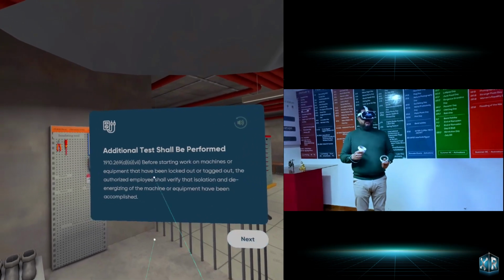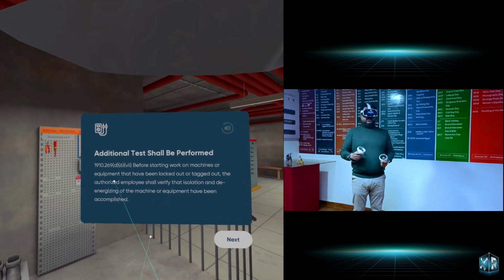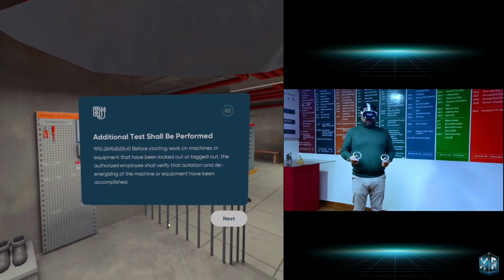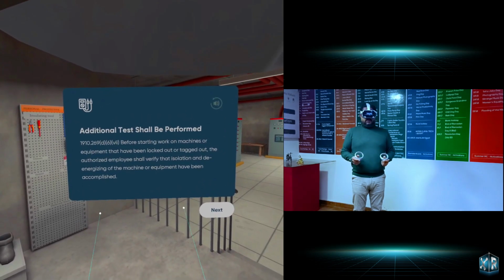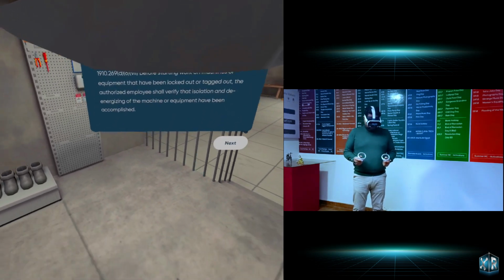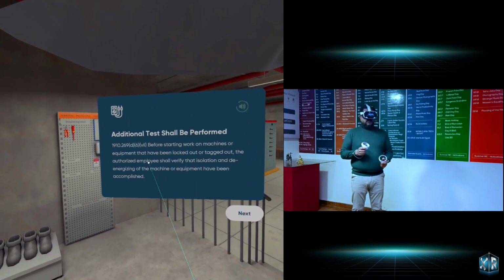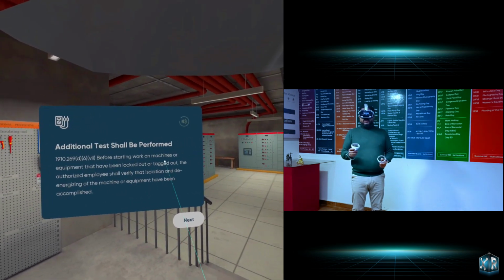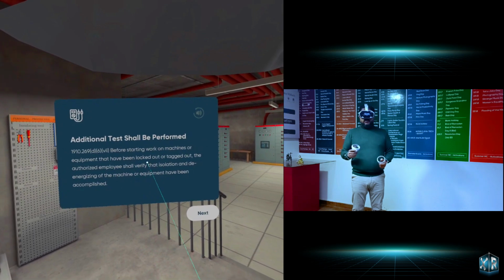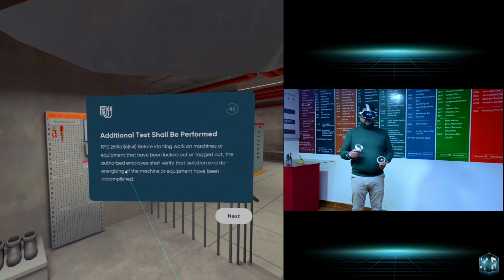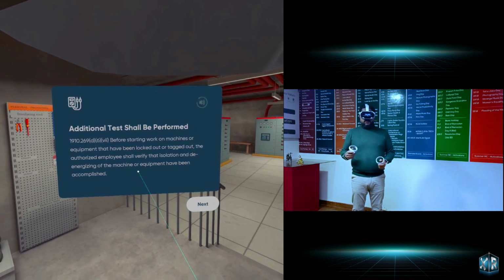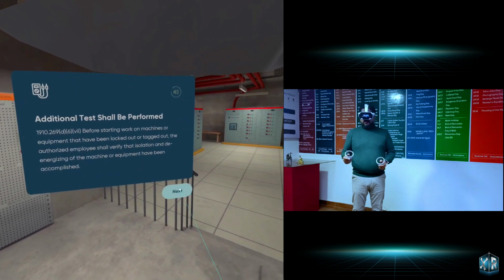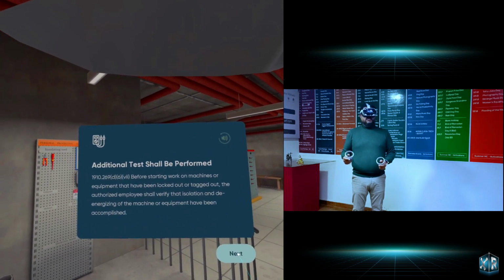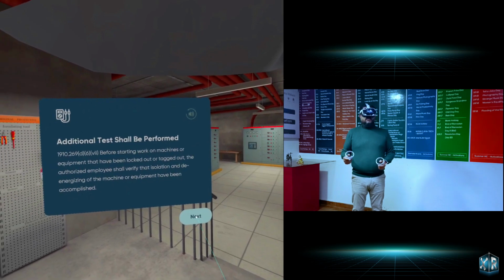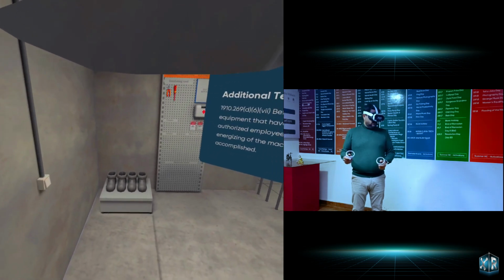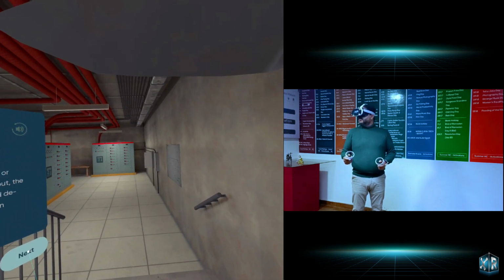The additional test shall be performed. After switching off the circuit breaker on the switchboard panel 3, an additional test shall be performed to verify that isolation and de-energizing of panel 1 were accomplished. According to the OSHA standards, before starting work on machines or equipment that have been locked out or tagged out, the authorized employee shall verify that isolation and de-energizing of the machine or equipment has been accomplished. If normally energized parts are exposed to contact by an employee while the machine or equipment is de-energized, a test shall be performed to ensure that these parts are de-energized.